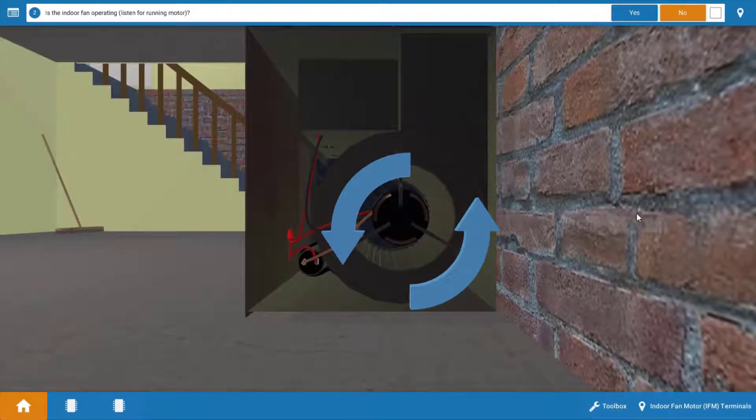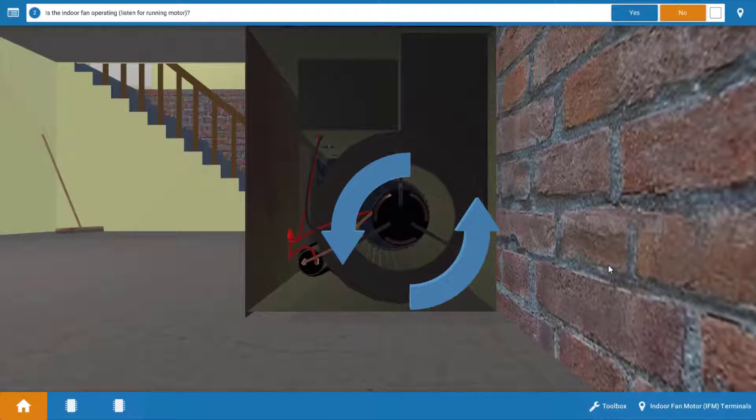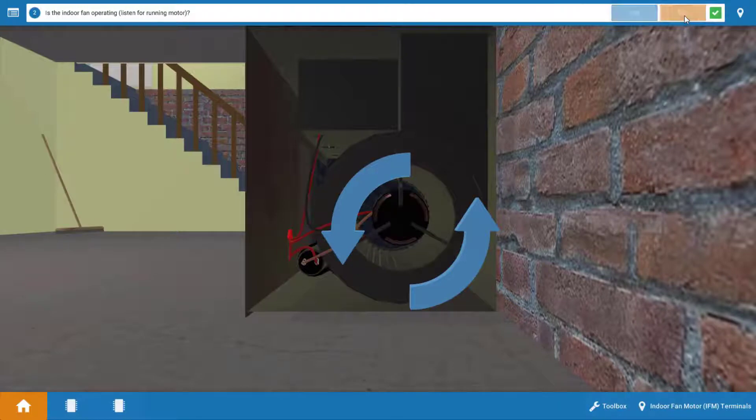Next, we want to take an inventory of which electrical loads are running. And if we look here, the indoor fan is not operating. Now, you'd be able to hear it running, or if you don't have speakers, these blue arrows would be spinning if the fan was running. So no, the fan's not running.